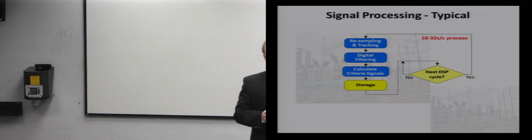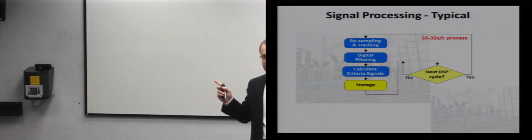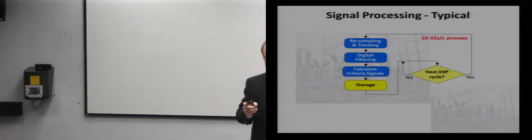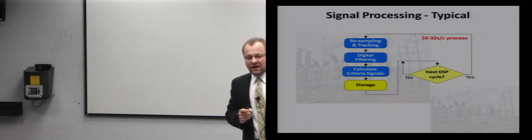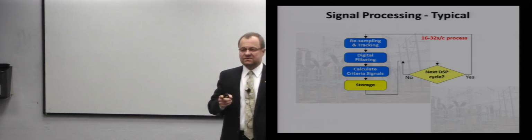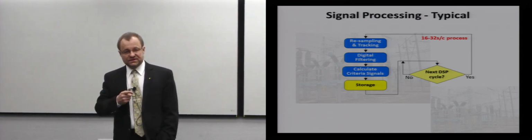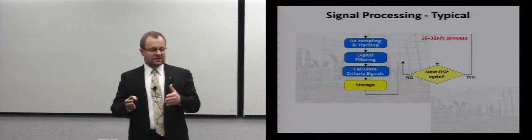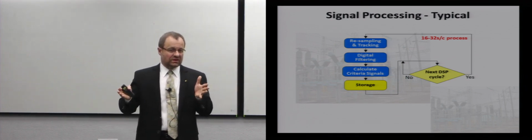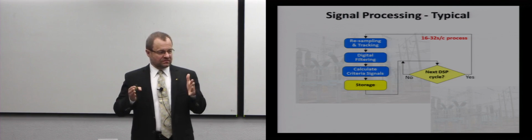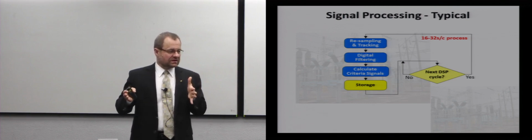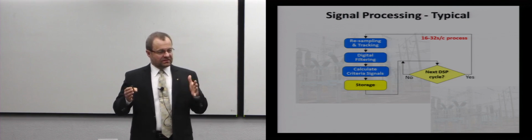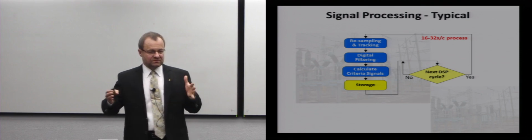So what we did as an industry is we ran this process at a variable rate. We track frequency, and we do it so many times in every power system cycle. Power system cycle is 16.66 milliseconds nominal in North America, right? So we do it, say, roughly every 1 millisecond, but it's variable. If the frequency moves, that process moves.